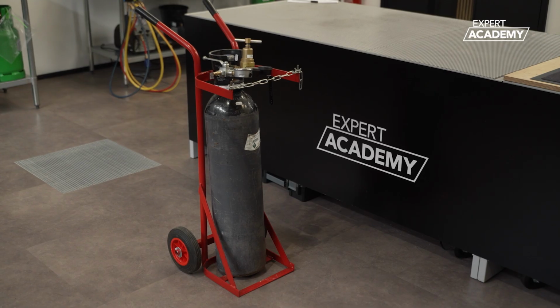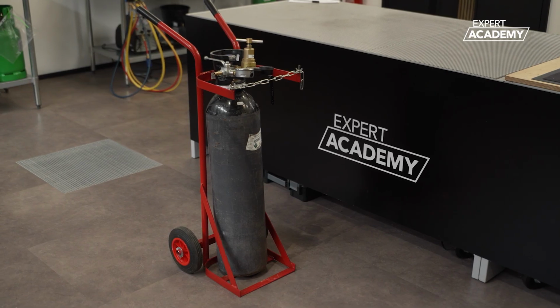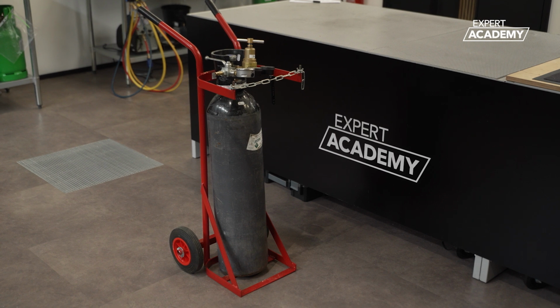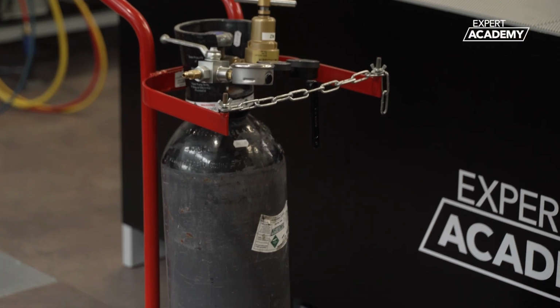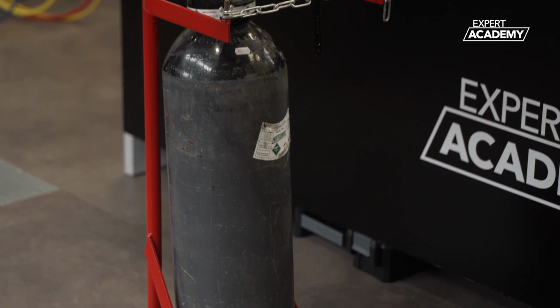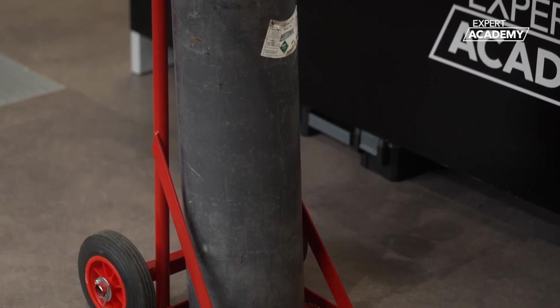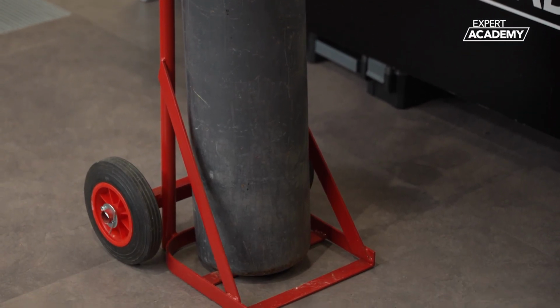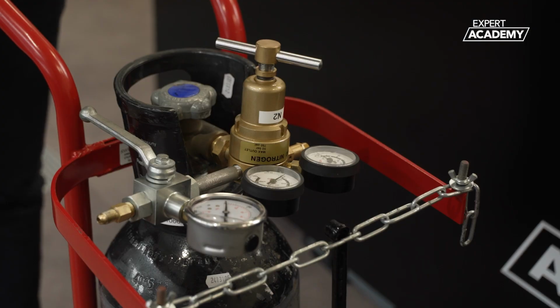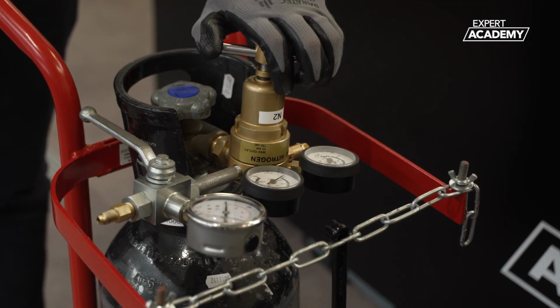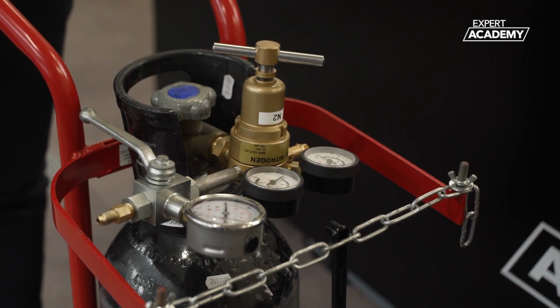Nitrogen is used to pressurize a refrigerant circuit for performing pressure tests on refrigerant lines and components before adding any gases. It is inert, meaning it is non-reactive chemically, non-flammable and stable across a range of temperatures. Therefore, it is well suited for pressure testing and is readily available at low cost. Nitrogen is also used during brazing to prevent oxidation. Dry nitrogen is flowed through the tube during brazing to displace oxygen and prevent scale formation.